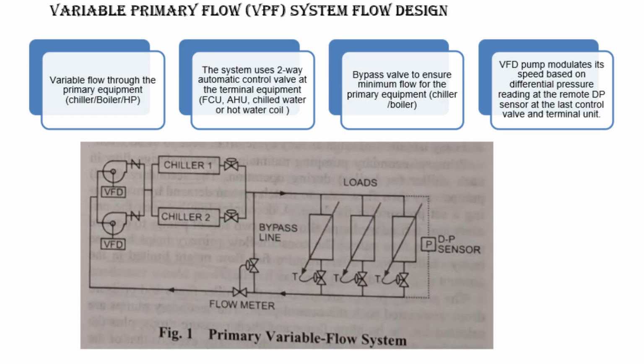First, variable speed pumps are installed on the primary loop. These pumps are equipped with VFDs that modulate their speed based on system demand. Next, the flow passes through the chillers, boilers, or heat pumps, depending on whether the system is used for cooling or heating. Because the flow is variable, two-way automatic control valves are installed at each terminal unit, such as fan coil units, air handling units, or hot water coils.